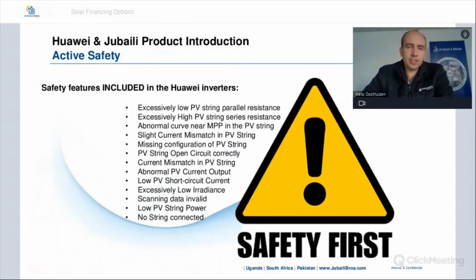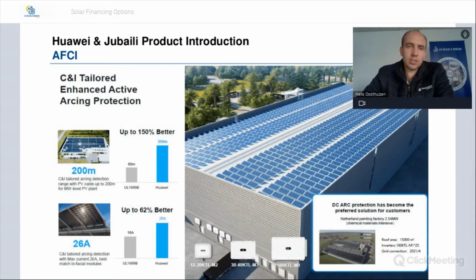Some of the safety features included as standard in Huawei inverters. This is just a list of common problems that the inverter can pick up: excessively low PV string parallel resistance, excessively high PV string series resistance. I'm not going to go through all of them. Current mismatch in PV string, abnormal PV current output, excessively low irradiance, low PV string power. For all of these safety features or errors it can pick up, the inverter will specify what the fault is, and it will also specify a possible solution for you. This is all standard, available in the manual or on the app. But if you do have any problems with any inverter where it gives you a specific error code which you're unsure about, please send it through to us and we will see how we can assist you.